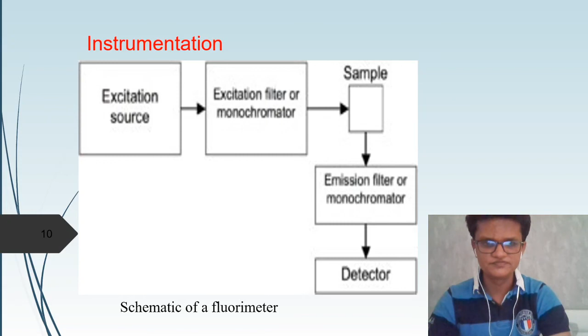Then that light travels towards the sample, and the sample again emits radiation. That emitted radiation is converted from polychromatic light to monochromatic light by the emission filter, and that light is measured with the help of the detector. Now, in fluorescence spectroscopy, you have to remember that the detector is always arranged at a 90-degree angle.